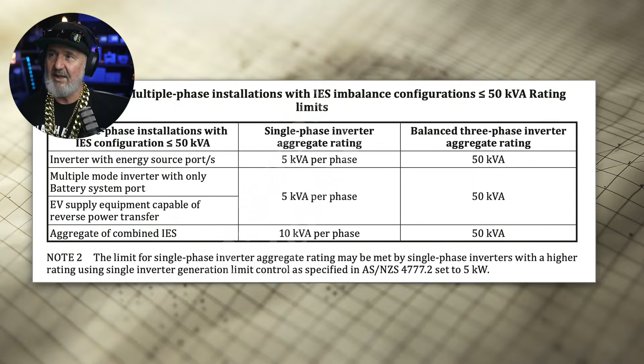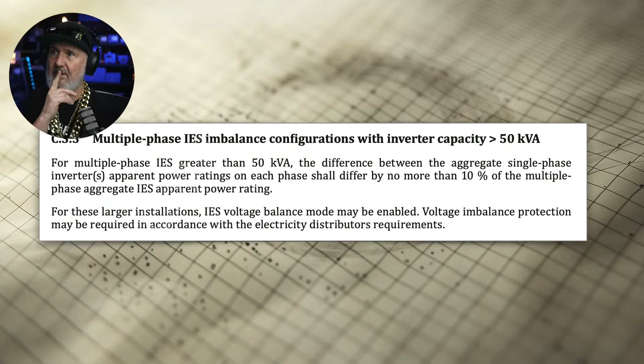For multi-phase inverters greater than 50 kVA, the difference between the aggregate single-phase inverters' apparent power on each phase shall differ no more than 10%. What that means is you're not putting a 3 kilowatt inverter and a 10 kilowatt inverter on different phases. They need to be balanced across the phases. So phase balancing is the intent of this. Now, New Zealand does have that very peculiar rule where metering is done on a per phase basis. I think it's probably still true. It's only two countries in the world that do this, the Czech Republic, or Czechia now, sorry, they changed their name, and Aotearoa New Zealand.